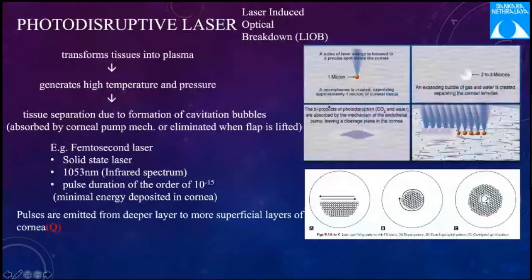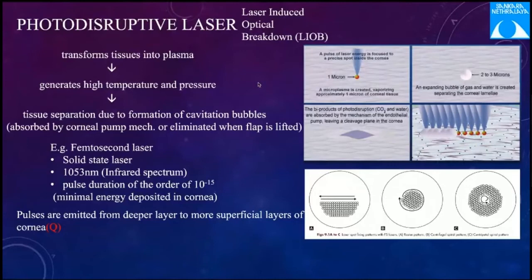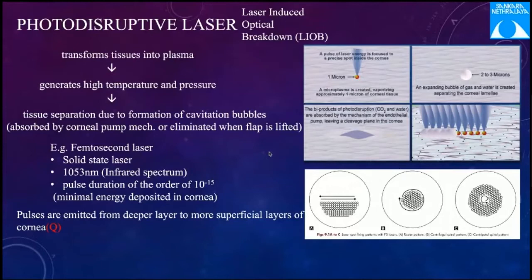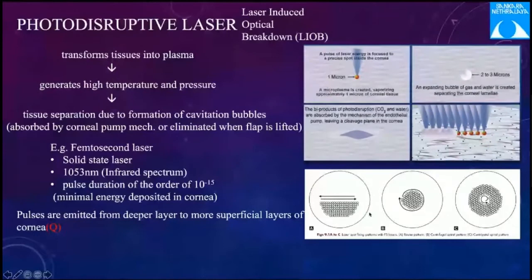The photodisruptive laser uses a highly focused beam thrown onto the cornea, resulting in plasma formation which expands rapidly, separating tissue planes and forming cavitation bubbles. These bubbles are absorbed by the corneal pump mechanism or eliminated when the flap is lifted — known as laser-induced optical breakdown. The femtosecond laser is a solid-state laser emitting at 1053 nm in the infrared spectrum, with pulse duration of 10 to the power of minus 15 seconds, depositing minimal energy. Pulses are emitted from deeper to more superficial layers; three patterns include raster, spiral-out, and spiral-in. The spiral-in pattern maintains centration with the laser light until the very end of the disruptive procedure.